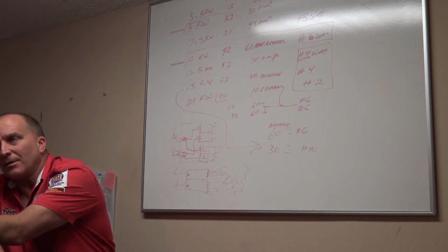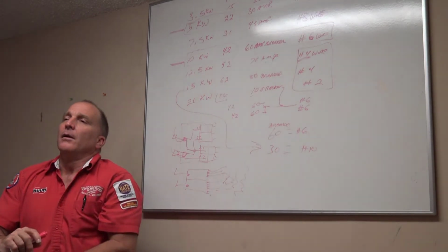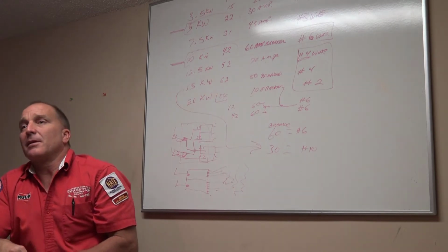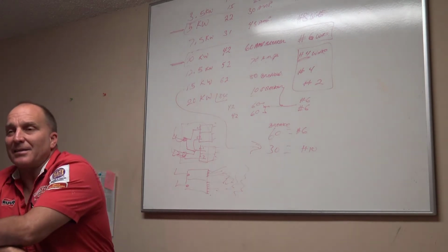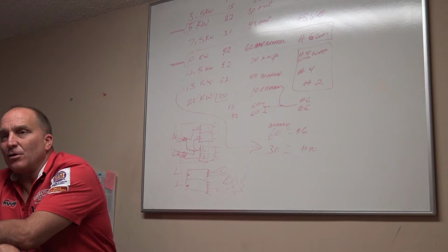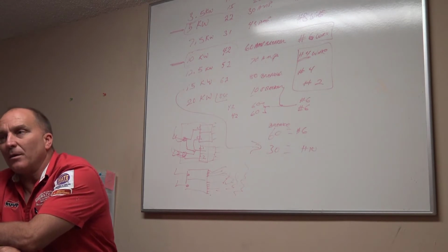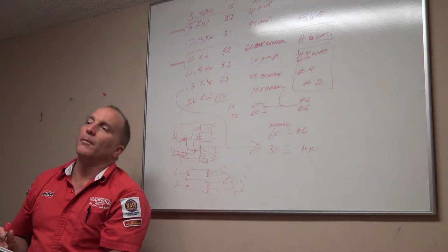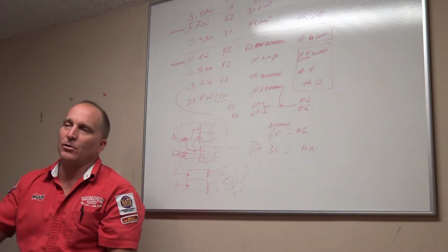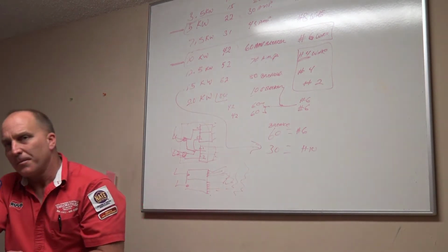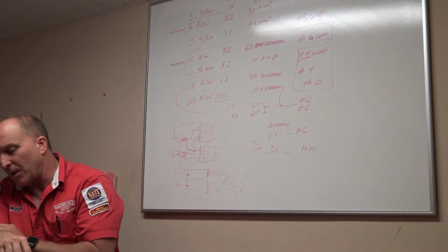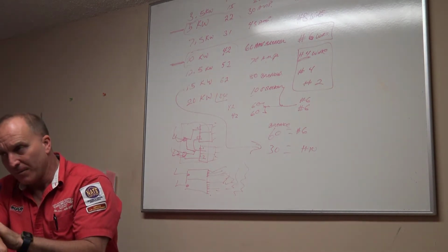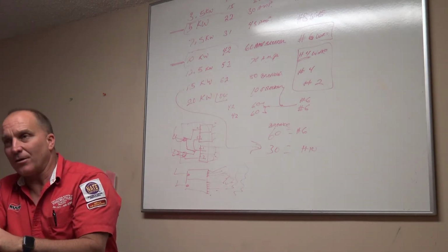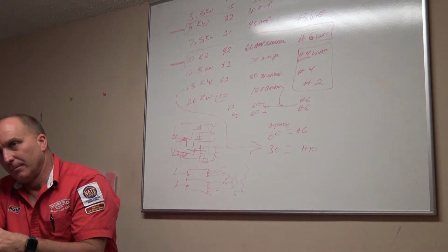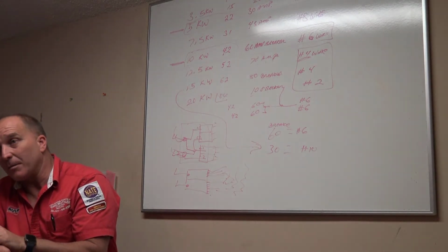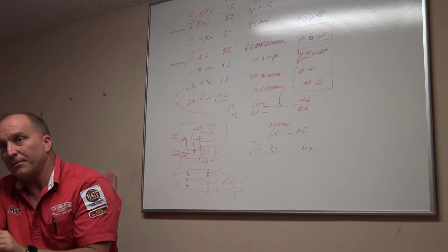Now you have to go check to see what condenser you have, what tonnage it is, how many CFMs you have, and is that CFM correct for that specific tonnage, and do you have to increase or decrease the blower speed of that particular unit running in cooling mode. Then you turn it back into the heating mode and put it on the lower speed where you originally had it designed to, and then you check your delta T in the heating mode. The delta T in the heating mode should be between 35 and 55.